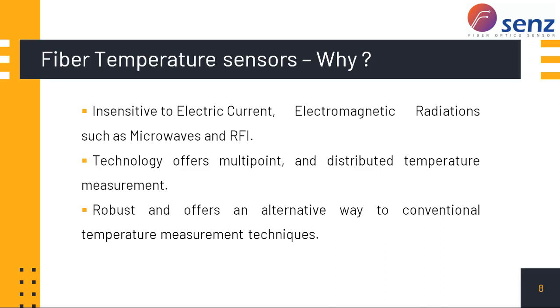The second reason is the fiber temperature sensor offers multi-point temperature sensing on the fiber, multiple sensors, and we take the reading in case of fiber grating. With the Raman effect, we will get, for a very long length, maybe 10 kilometers, the temperature every 1 meter. So the applications are quite different from what we can attempt with normal contact type or non-contact type temperature solutions. The third major topic is that it is a robust technique compared to the conventional. So these are the three major areas, and we will go through each of these types of sensors, as I told you in the last slide.